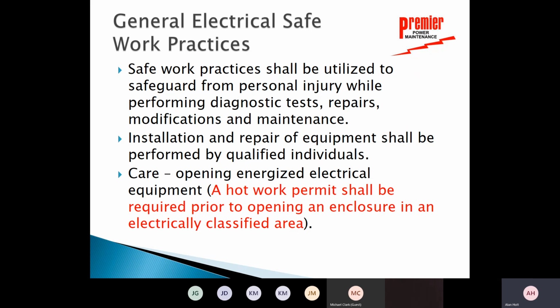But basically mentioned in their section is while performing diagnostic tests, while performing repairs, and while performing maintenance and modifications. So the diagnostic tests are where we're going to be concerned. And we've actually found a couple, 3 times on various sites where electrical work clearance, safe work clearance was supposed to have been in place for us, and we found some stuff still energized, some backfeeds. So it's important that we as a contractor stay on top of that.